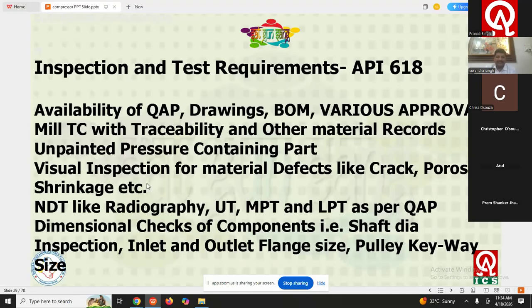Again, visual inspection. After the certificate and the TC review, the inspector will do the visual inspection for visual defects in the casting: crack, porosity, shrinkage. Then he will carry out the NDT as per the approved QAP, that is radiography, if applicable, UT, MPT and LPT, if applicable. All four NDT methods are reflected in API 618. So it is up to the user which kind of NDT method is reflected in their QAP. So the inspection engineer must follow the respective QAP.